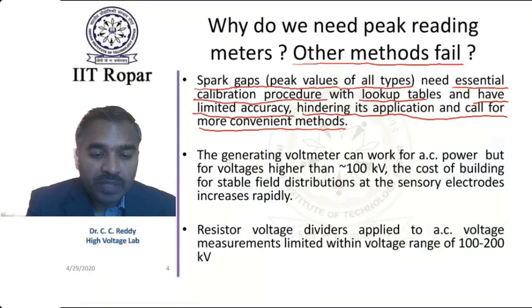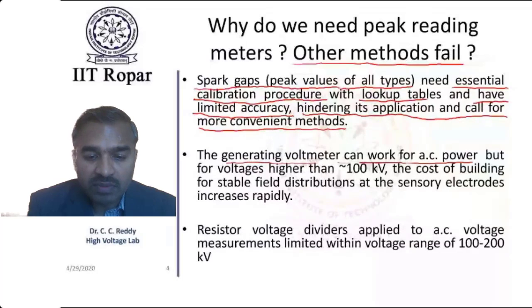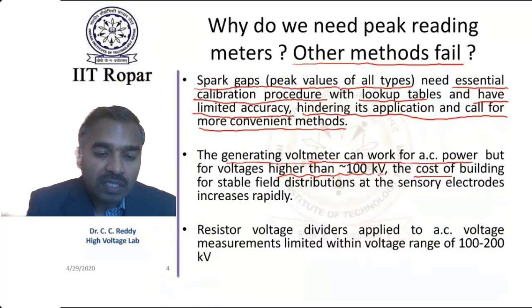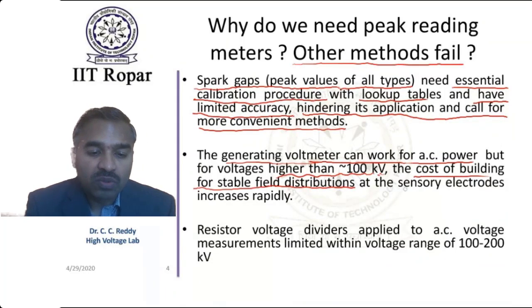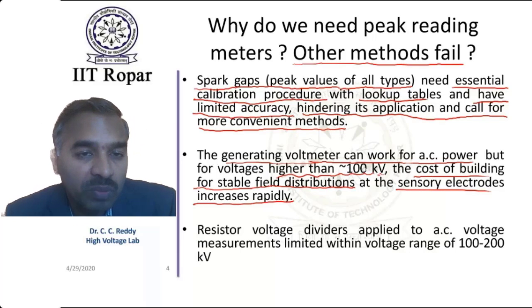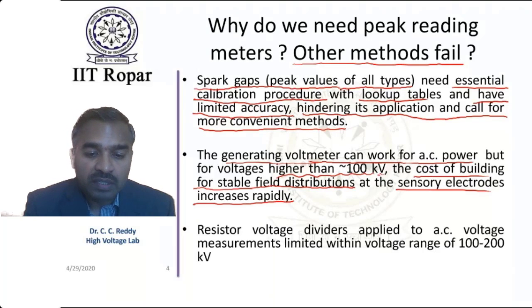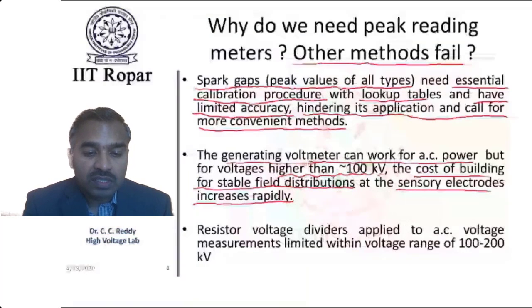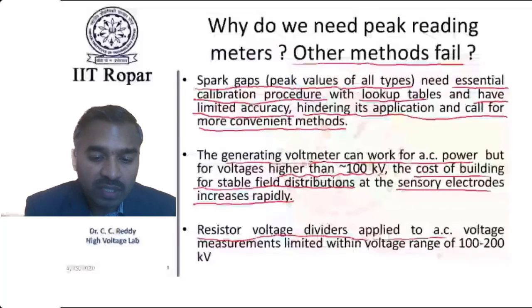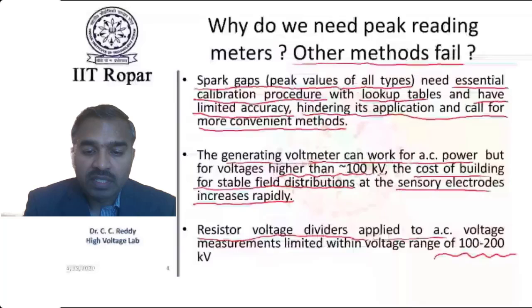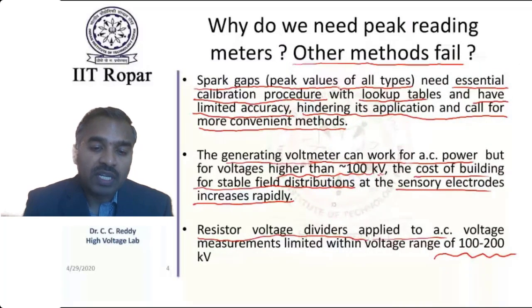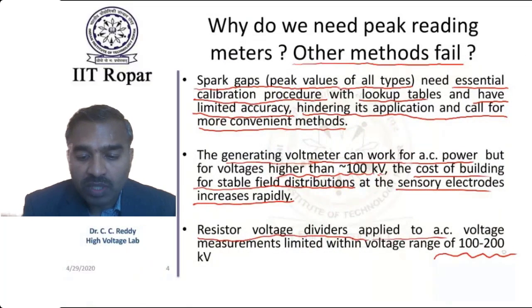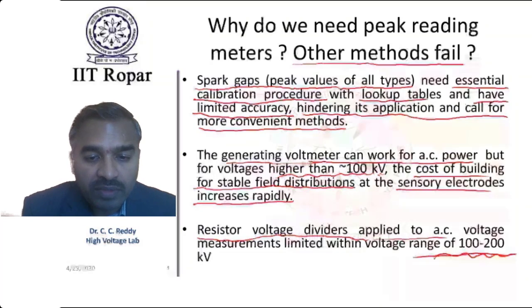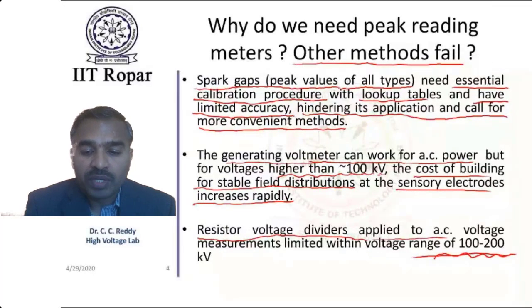So what about generating voltmeters? Generating voltmeters can also work for AC, but when the voltage is higher than 100 kilovolts, the design becomes complex and cost increases, because the cost of building stable electric fields at the sensing electrodes increases rapidly. So up to 100 kilovolts, generating voltmeters can be used for AC, but beyond that additional cost is incurred. And we have seen the limitations of resistive dividers. They are also limited to around 100 to 200 kV due to limiting currents, heating effects and stray capacitance effects. So for voltages even higher than that, we do need peak reading meters.